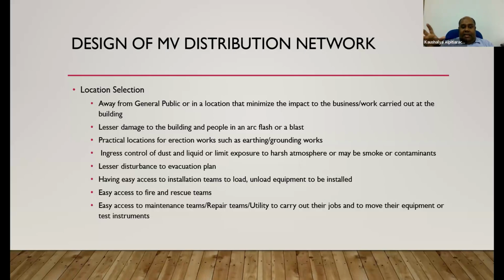Practical locations for erection works and earthing and grounding. So we have seen some installations where the entire building is distributed on the land, leaving no space for your earthing, or sometimes evacuation, or to reach fire people, or maybe to load, unload spare parts, or to replace one of the medium voltage switchgear. That creates a difficult situation.